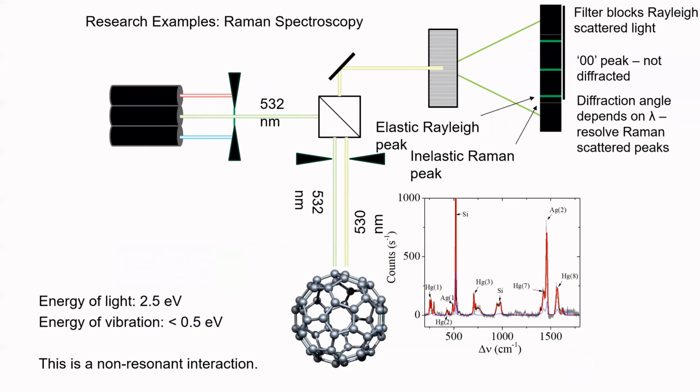Okay, so this is how it actually looks in practice. This is a rough schematic, as it turns out, of the Raman microscope in the condensed matter labs. So we start on the left there, we have lasers, and our system has 3 lasers. So we've got a blue laser, a green laser, and a red laser. And you can choose different lasers for looking at different materials. And that's to do with how easy it is to access the virtual state, the virtually excited state.